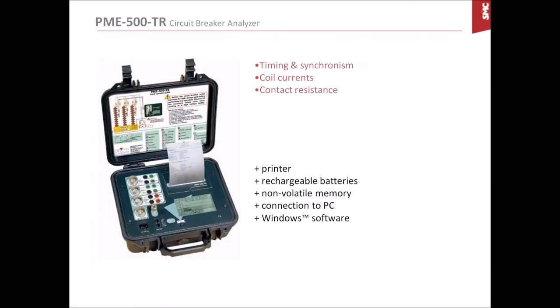This is the instrument we are using, the PME500TR. This instrument is basically a precision timer. It is able to register timestamps for any change in the main contacts and two auxiliary contacts, with a resolution of one tenth of a millisecond. It will also make a graph and record coil currents sampled at the rate of 10 kHz. It will also measure the contact resistance in the main contacts when they are closed. You also have built-in batteries, which allow you to use the unit with no mains AC. It has onboard memory to save the results.